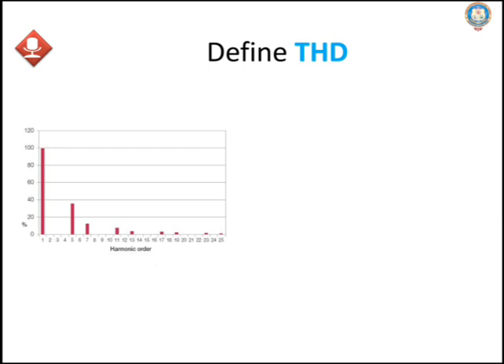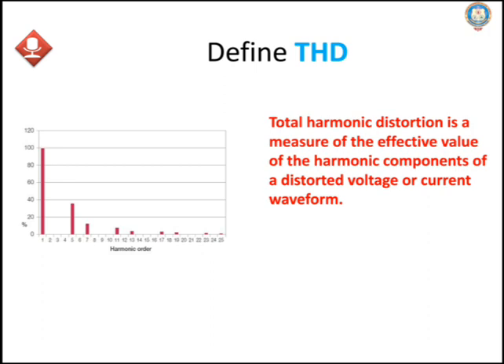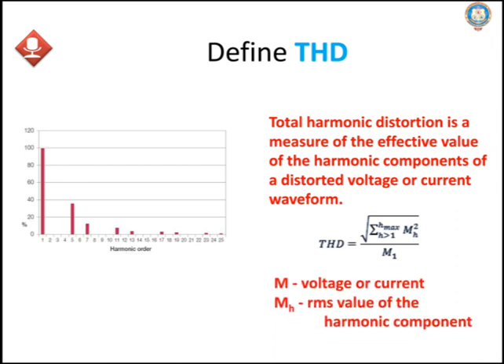Define Total Harmonic Distortion. Total Harmonic Distortion (THD) is a measure of the effective value of the harmonic components of a distorted voltage or current waveform, given by THD = √(Σ from h>1 to h_max of Mh²) / M1, where M1 refers to the fundamental voltage or current and Mh refers to the RMS value of the harmonic component.